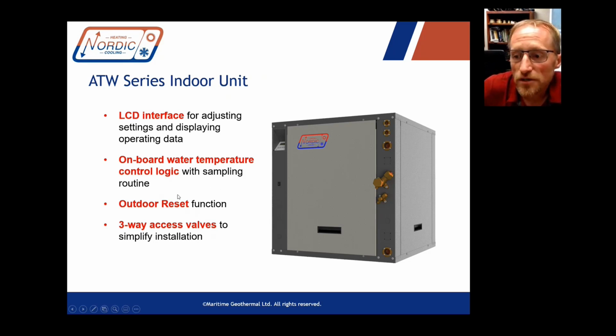There's onboard water temperature control logic. So the heat pump, without any external thermostat or aquastat, has the ability to monitor the buffer tank temperature and maintain it to a user selectable set point temperature. And you would, of course, choose different water temperatures depending on what your hydronic distribution system was.